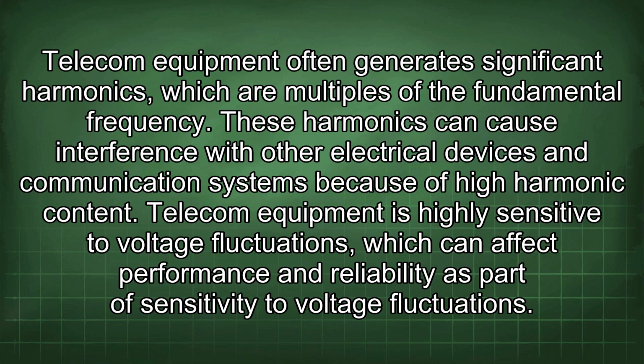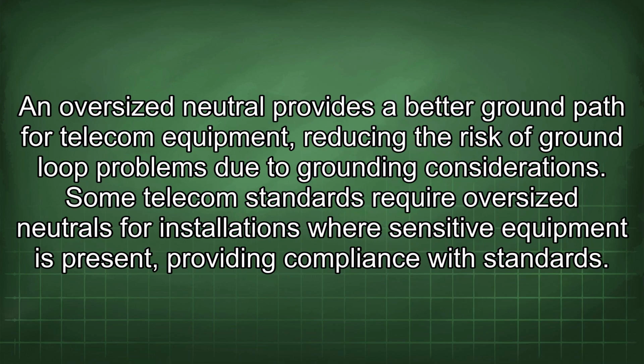These harmonics can cause interference with other electrical devices and communication systems because of high harmonic content. Telecom equipment is highly sensitive to voltage fluctuations, which can affect performance and reliability. An oversized neutral provides a better ground path for telecom equipment, reducing the risk of ground loop problems due to grounding considerations. Some telecom standards require oversized neutrals for installations where sensitive equipment is present, providing compliance with standards.